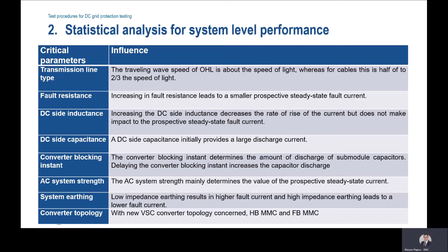Let's look at one of these criteria, for example, how we perform the statistical analysis for system level performance. Within RTDS, it is possible to design a C code, and in this code we can provide automatic testing of the relays by continuously changing particular parameters. On the left-hand side we see the flowchart of changing these parameters. On the right-hand side, based on the selected parameters, we can perform in this case 4,500 tests, meaning 4,500 operation times that we can classify into classes from 1 to M, where class 1 will be the minimum operation time, which is 1.5 milliseconds, and this class increases by 300 microseconds.